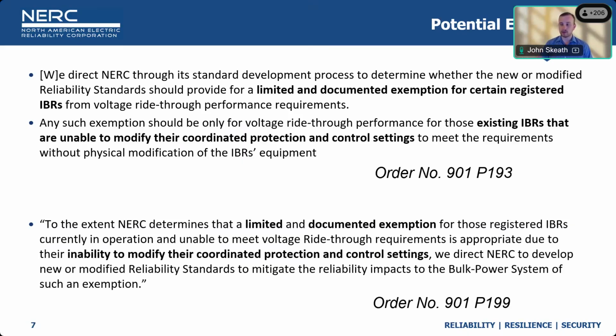I also wanted to cite that there were some potential exemptions that were already baked into the 901 language. Those are limited and documented exceptions for certain registered IBRs. They concluded the sentence from voltage ride-through performance requirements, but the additional bullet I want to have here is that it's for existing IBRs that are unable to modify their coordinated protection and control settings in order to meet those requirements.